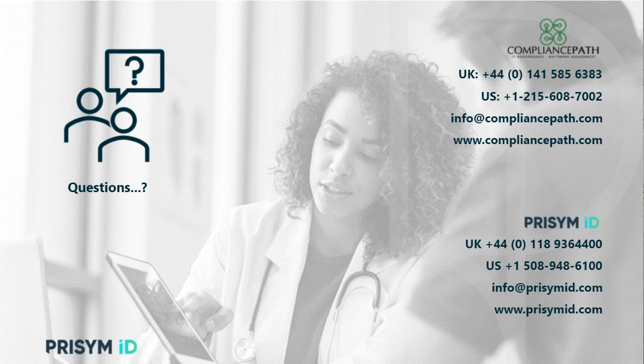Great, thank you, Doug. We've had a question about validation master plans, and I wonder, Phil, can you describe what a validation master plan should look like? Yeah, the validation master plan starts to lay out how you're going to meet your regulatory obligations. It'll start to examine at the beginning, what's the purpose of the system, what are the objectives, are there user requirements, what are we trying to meet, or what business cases we're trying to meet. It'll lay out that kind of information.